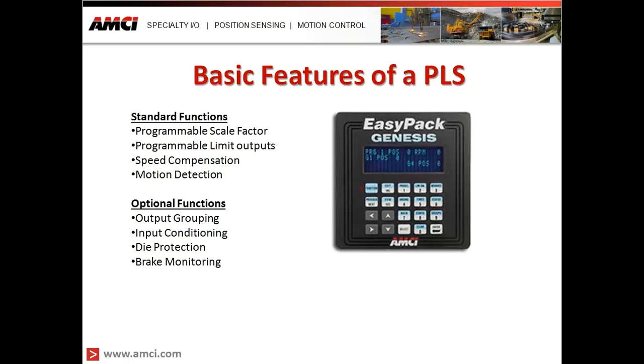Speed compensation adjusts the timing of the limit outputs internally so that as machine speed increases, the position at which those outputs turn on and off remains mechanically the same on the machine. Another standard feature is motion detection, which can be used as a safety feature — it monitors position feedback from the sensor, and if that feedback stops, an output turns on to alert the operator or automatically stop the machine, such as when a sensor cable breaks.